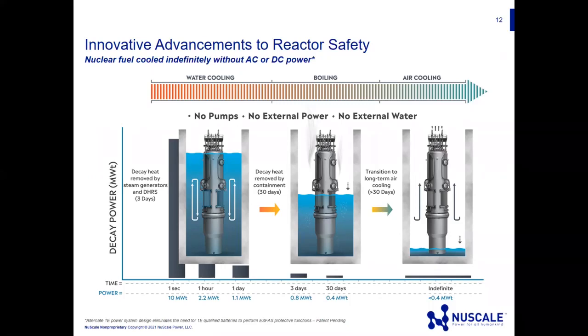The first 3 days, when the decay heat's highest, we basically assume we boil off all that water. Then as the decay heat goes down, we can just have air cooling. So by 30 days, when the water is gone, the decay heat's low enough that all that's needed is just the natural air cooling. This is why we say you can cool it indefinitely without sources of power.